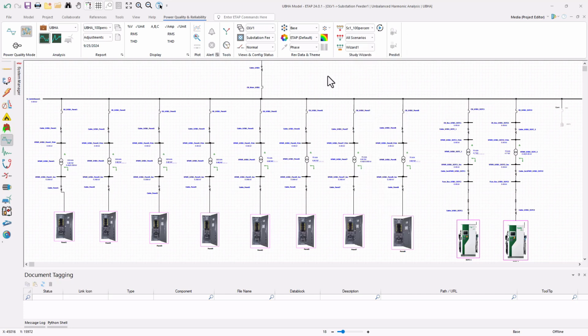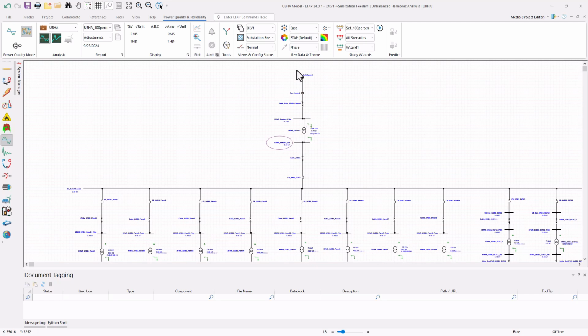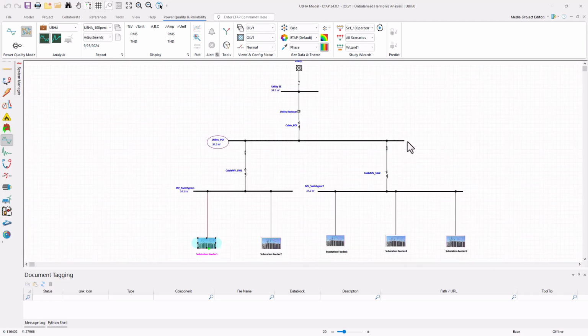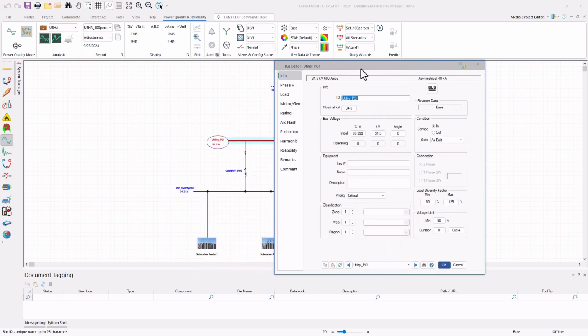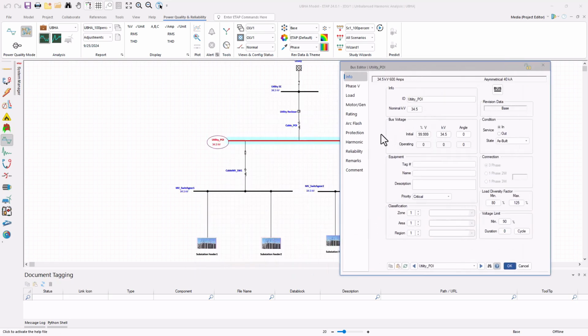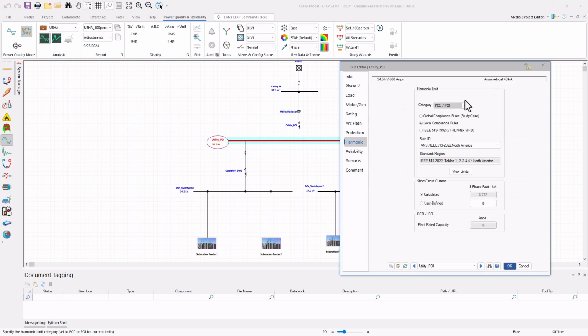6 PCC locations, point of common coupling locations, were analyzed to evaluate the harmonic distortion levels coming from the EV charging facilities towards the utility network. These locations have been highlighted with ellipses around. So let's take a look at one of those buses. One is the utility bus feeding the medium voltage switchgears. If we go to the harmonic page, we'd see it set up as PCC/POI with the rulebook set up to compare the harmonic distortion results with the limits from this rulebook.